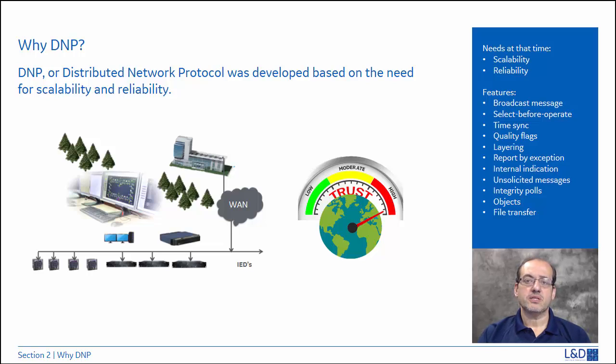So this opened the way for other open protocols to start implementing something similar to an unsolicited message. So all of these great features: time syncing, which wasn't a strict thing that's available in a lot of other devices, and level of support, so devices could be at level 1 DNP or at level 2 DNP. And pay attention to this.